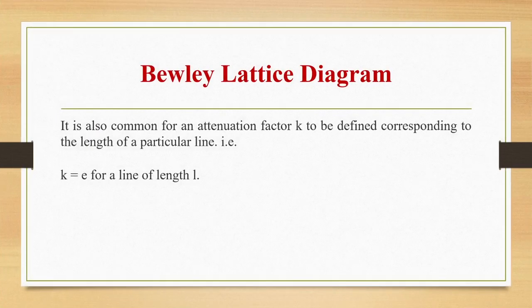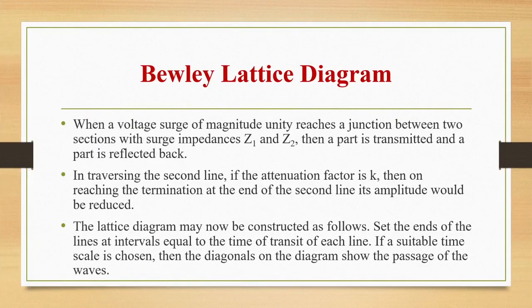It is common for an attenuation factor K to be defined corresponding to the length of a particular line, that is K = e^(−αL) for a line of length L. When a voltage surge of magnitude unity reaches a junction between two sections with surge impedances Z1 and Z2, a part is transmitted and a part is reflected back. In traversing the second line, if the attenuation factor is K, then on reaching the termination at the end of the second line, its amplitude is reduced.